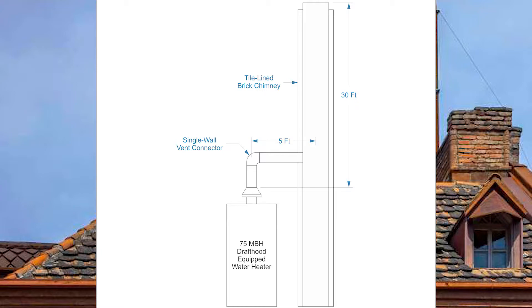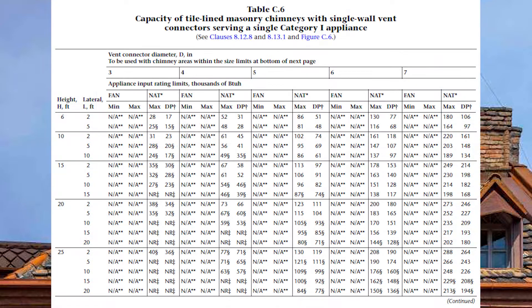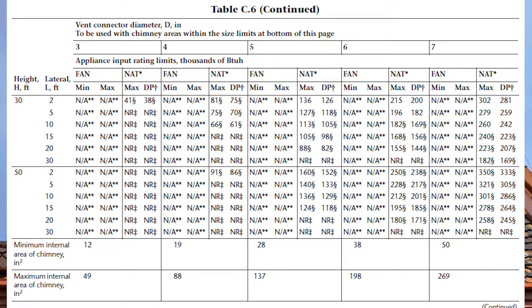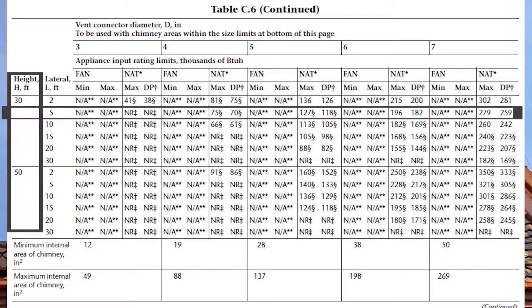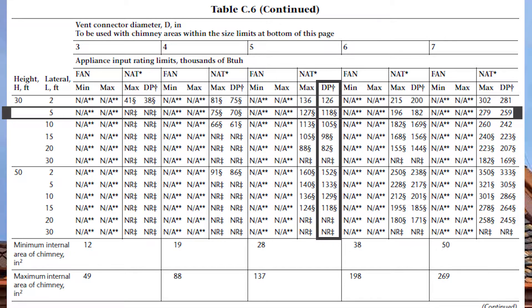Let's jump right into the example. I've got a 75 mbh draft hood equipped water heater with a single wall vent connector, a five foot lateral, going into a 30 foot chimney. Because I have a single gas appliance with a single wall vent connector going into a chimney, I need to use table C6, starting on the second page for the 30 foot vent height. Coming down to 30 feet, across on the five foot lateral, going to NAT DP — 5 inch is good up to 118 mbh, but it has a very weird symbol beside it.